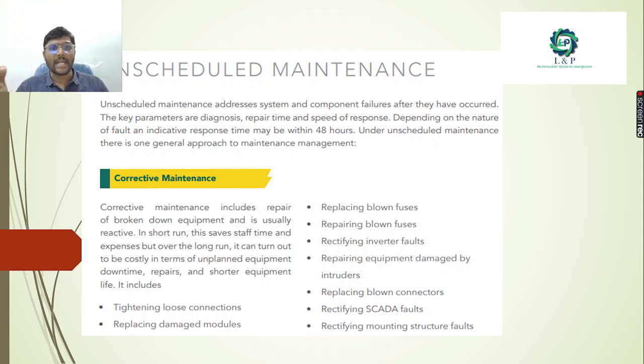So in unscheduled maintenance, we will check whether any loose connections need to be tightened. We need to replace any damaged modules, and most importantly we need to replace or repair any blown fuses, rectify the inverter faults, and repair the equipment damaged by intruders. Sometimes there is a possibility to replace blown connectors, MC4 connectors, and we need to rectify the SCADA faults and any mounting structure faults also.